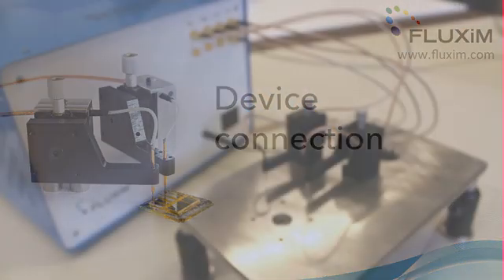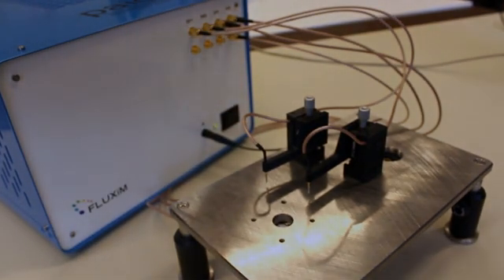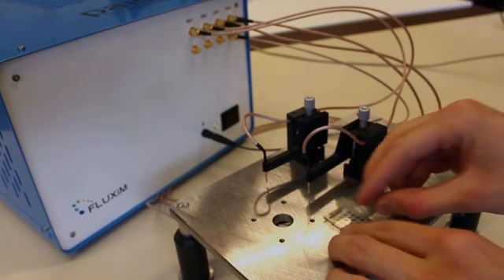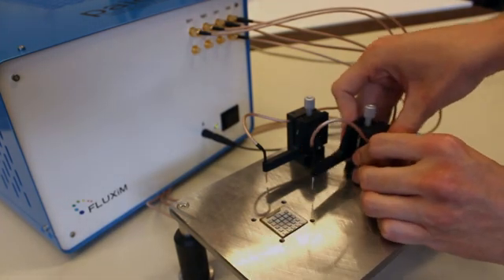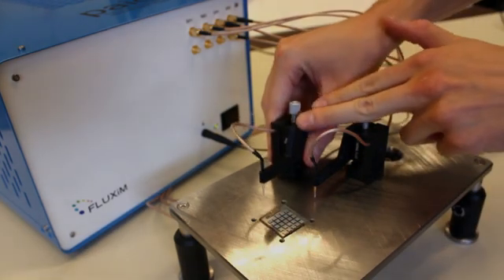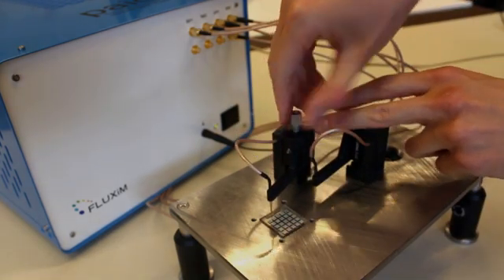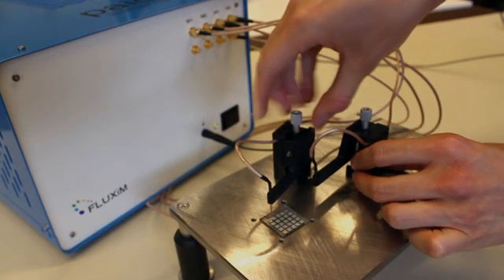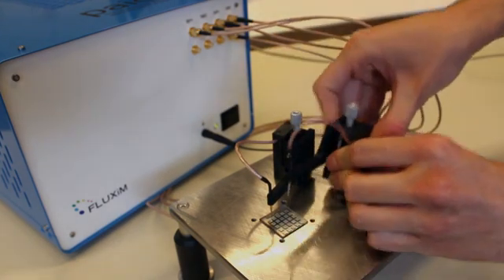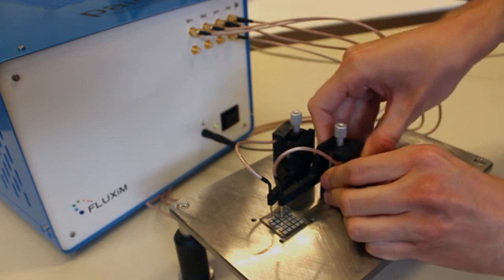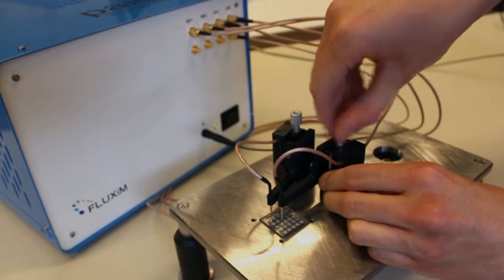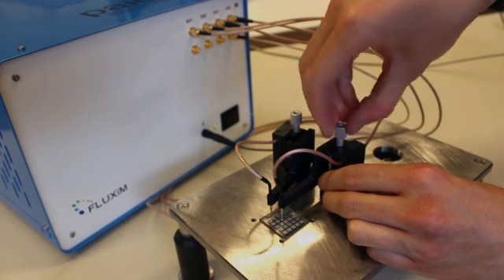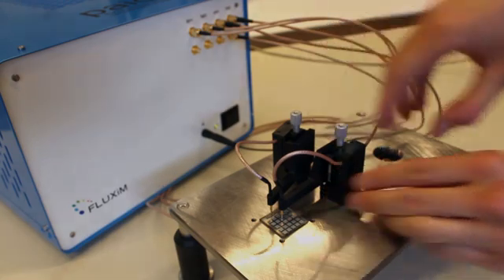Here you see the measurement table of Paios with the LED that is here below. We now connect a test solar cell to make some test measurements. This solar cell is a microcrystalline silicon solar cell. The surface is quite small, nine square millimeters. We developed these magnetic contacting probes to have a flexible contact that is well suited for transient measurements. A good contact is the key for a good transient measurement.